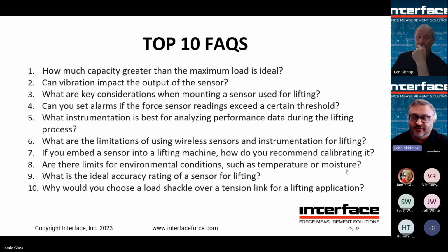Are there limits for environmental conditions? Absolutely. Extreme cold, extreme heat, moisture, all of those things are extremely damaging to sensors and systems that aren't rated for them. So it's important. It's not just an afterthought. What is the environment? Is it in a steel mill? It's going to be lifting a vat of molten steel. Well, that's important to know. Is it outside? Is it going to get rained on? Is it on a ship deck? Is it submerged below the ocean? Or is it freshwater or saltwater? How deep is it going to be? All of those things can be handled, but you need to know it going in, right? You don't just take a standard load cell or load pin and put it in a shackle down in the ocean without rating it for that.